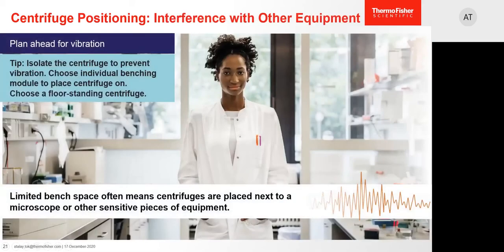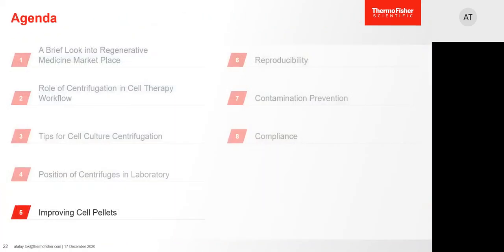Centrifuges inevitably cause vibration and shouldn't be placed on the same bench as microscopes or other fine instruments. Solutions include using centrifuges with casters or utilizing separate bench modules so there is no physical connection to fine instruments sharing the same bench space. Choosing the right equipment can already prevent many potential issues from becoming problems and gives you room for workflow improvement.